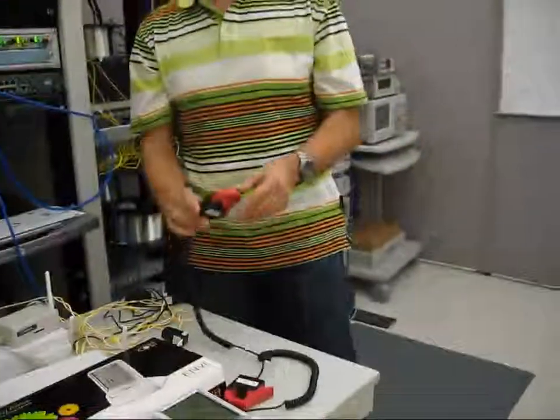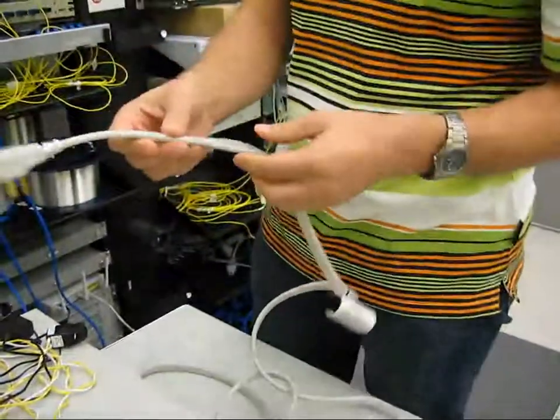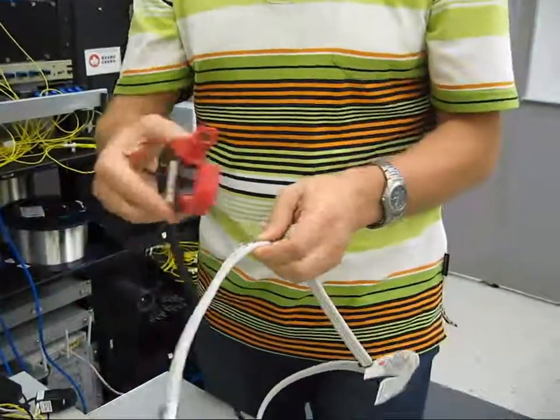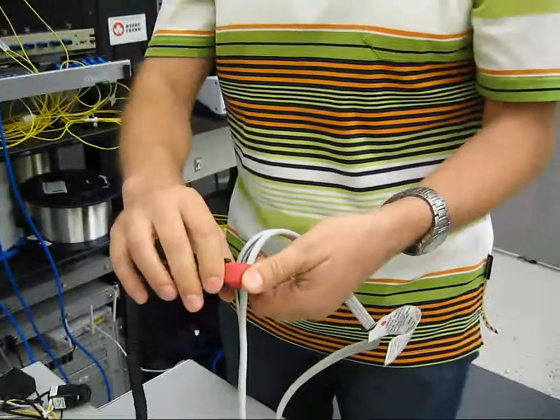The magnetic probes we use here to measure electric energy need to be attached around one hot leg only, not the neutral. The probe magnetic ring has to be very well closed, otherwise a part of the energy to be measured is lost. For example, let's take a look at the power cord. We need to know precisely which is the hot leg, and then attach the probe to that leg only, as tightly as possible, eventually even tie it up.